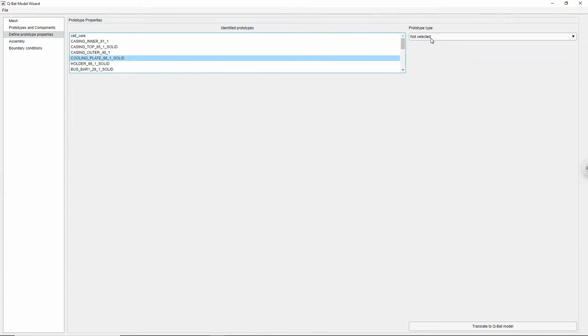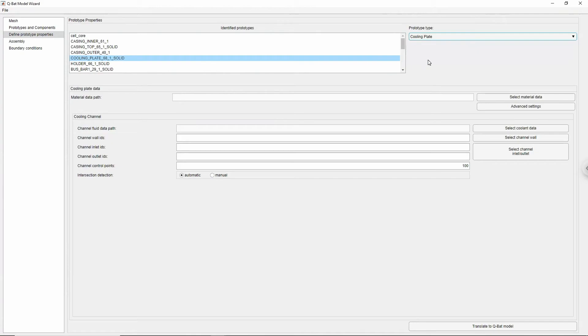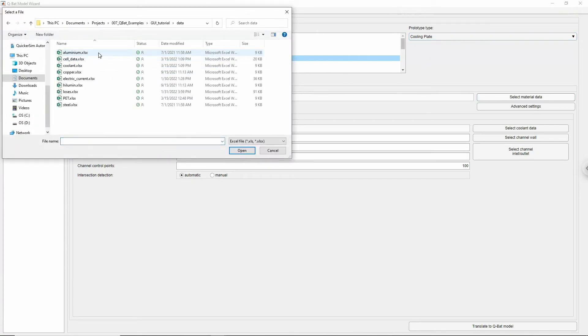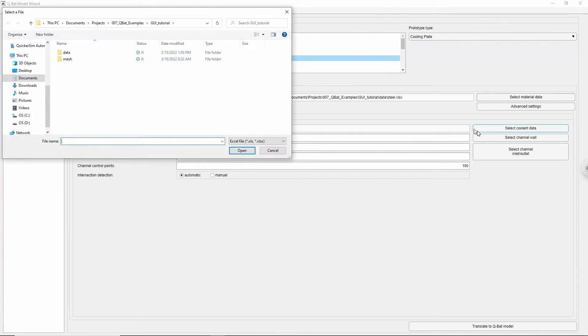Cooling plate is a solid body with a pipe inside where the coolant flows. The volume of the coolant is modeled as a void in the geometry. The cooling fluid is modeled as a one-dimensional fluid flow, and heat is transferred between the fluid and cooling pipe by the means of forced convection, where the heat transfer coefficient is calculated based on empirical formulas. When defining the material properties for the cooling plate, two different Excel spreadsheets are needed: one describing the properties of the cooling plate and the other for the coolant.